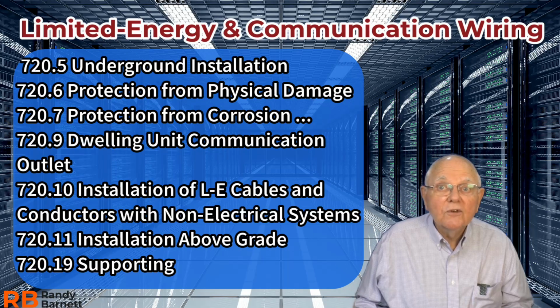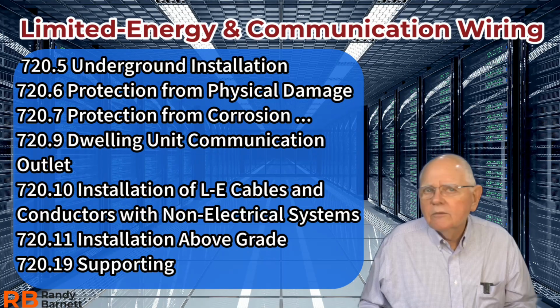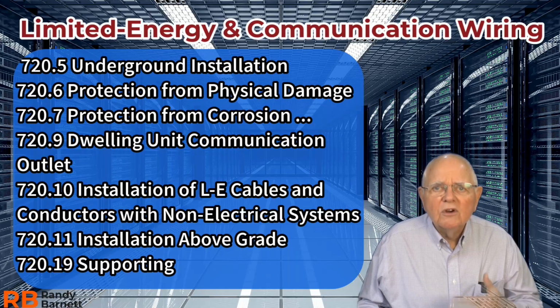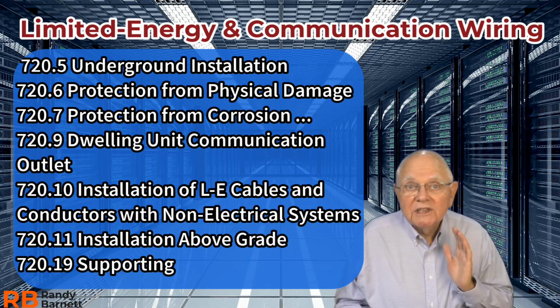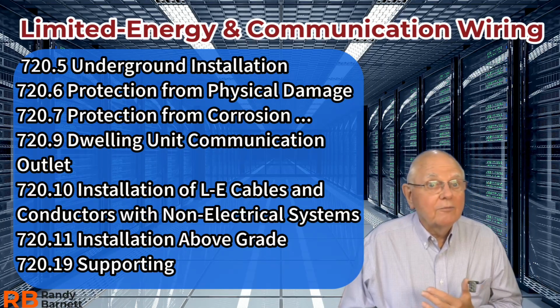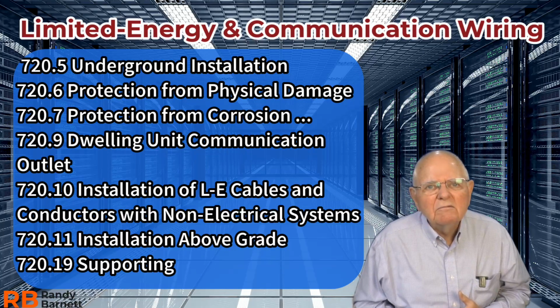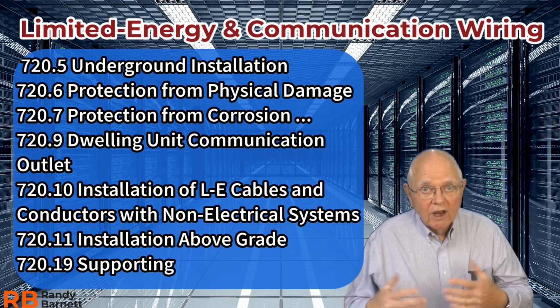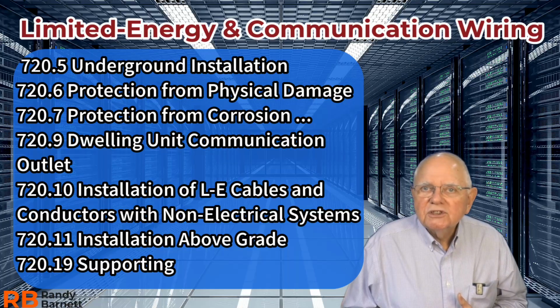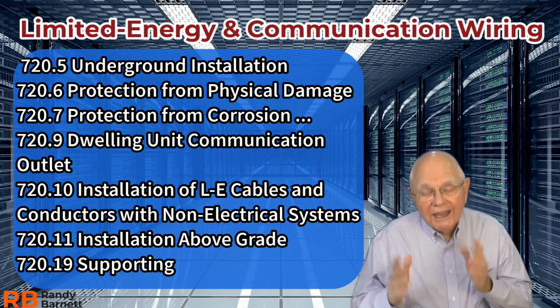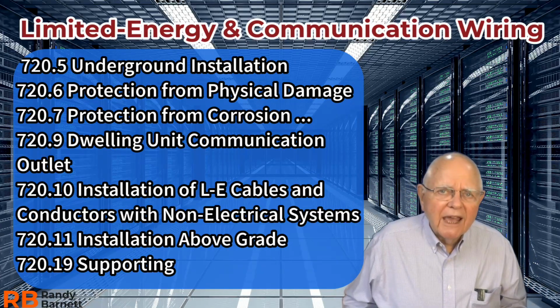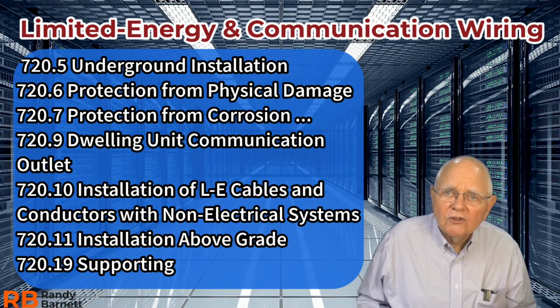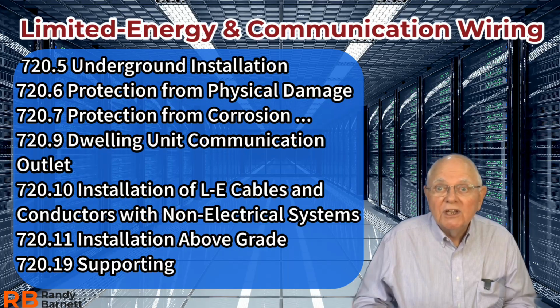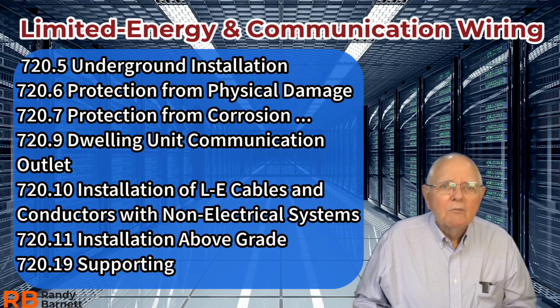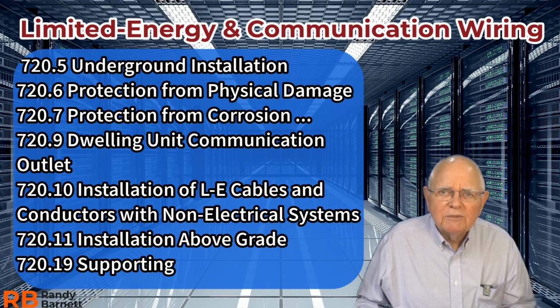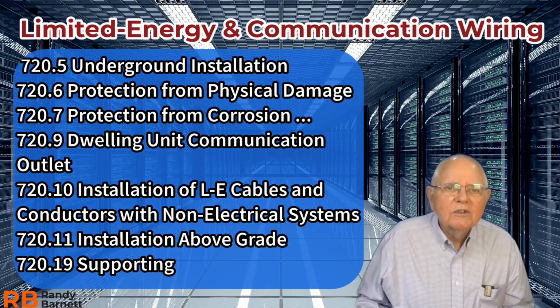Now, cables emerging from grade. We know the general rule is what? We're going to protect cables when they emerge from grade. Once again, there's an exception for fiber, communication cables, and coax. Also, 720.5 talks about, just like in 300, backfill. I've got to have clean backfill, no concrete, things like that in my backfill. I have to have a bushing, right, where I emerge from grade on that conduit, except for limited energy systems, a seal is permitted to be used in lieu of a bushing if it also provides that same amount of protection to prevent me from damaging that cable. Subsection G talks about earth movement. I lay my conductors in an S inside of that trench to allow for any earth movement. Directional boring: my cables or raceways, limited energy cables, raceways being used, must be approved for the purpose. Really same as in Article 300 then.